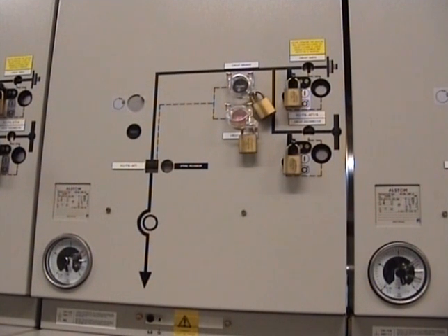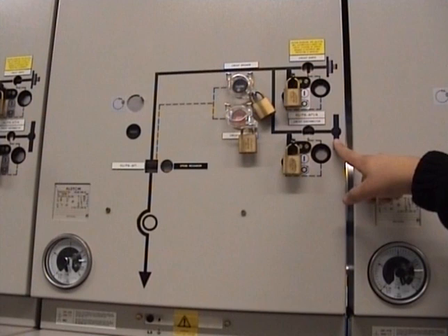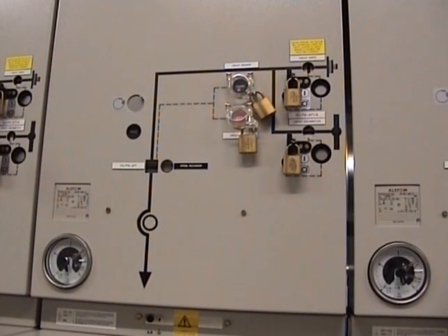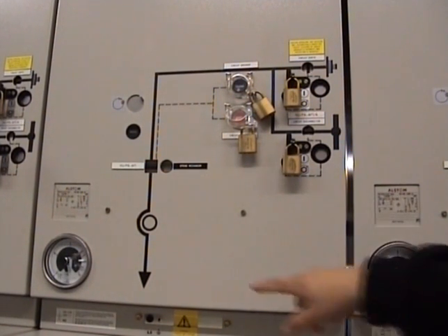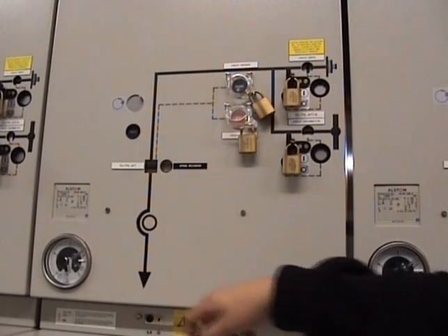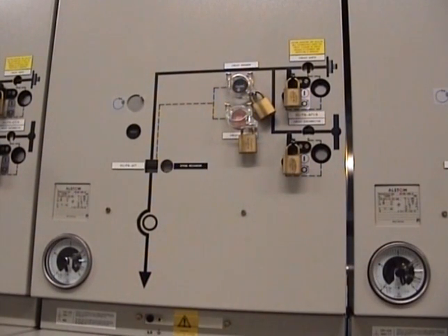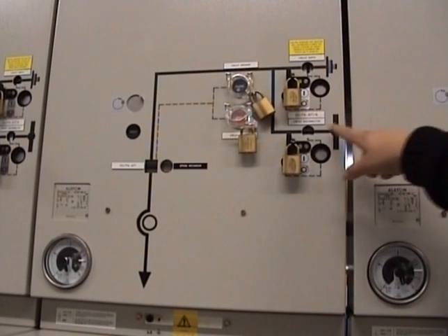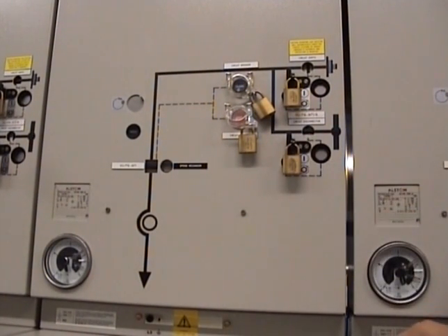Here we see the mimic for a single circuit breaker and disconnector and earth switch arrangement. On the right we see the bus bar, and on the left we see the outgoing feed. We see the bus bar disconnector, and above that the earth switch.